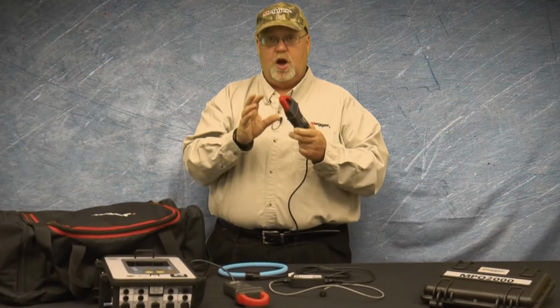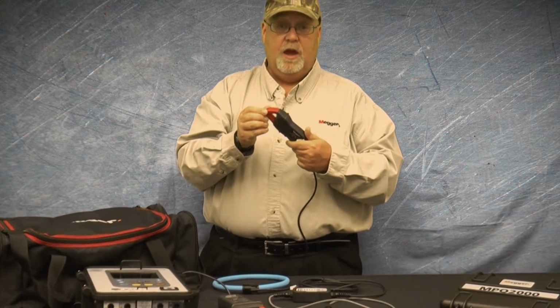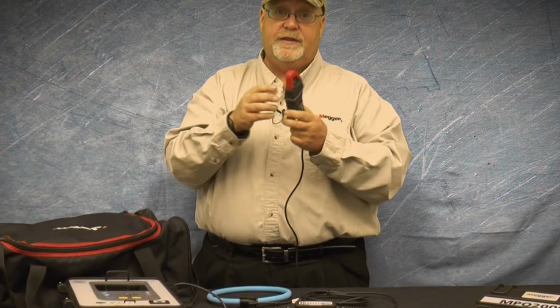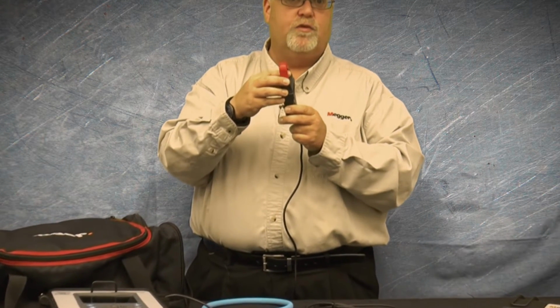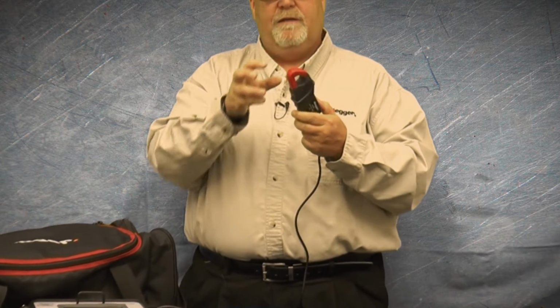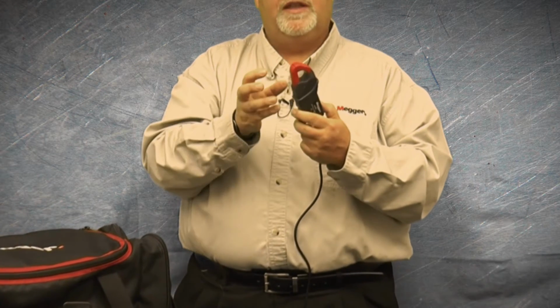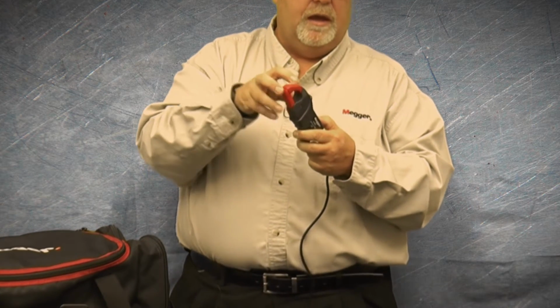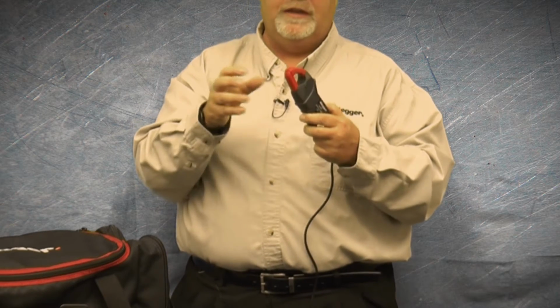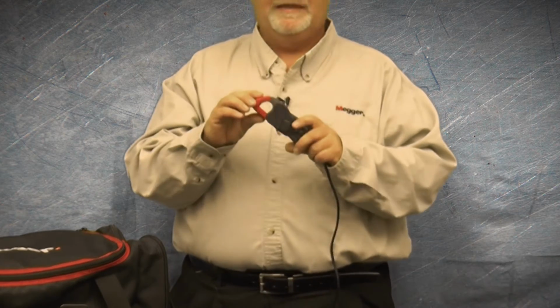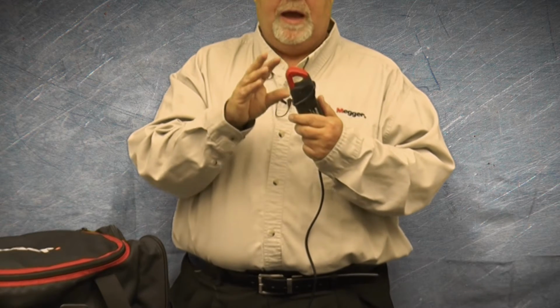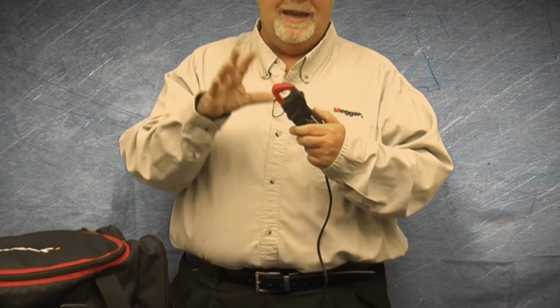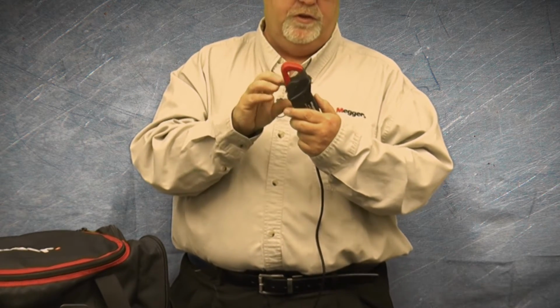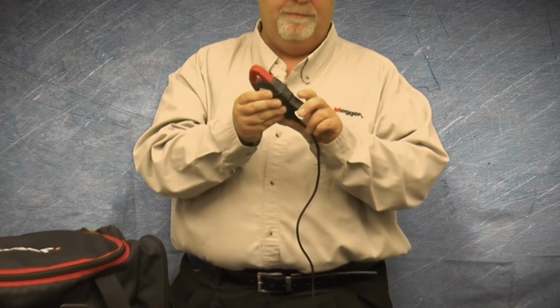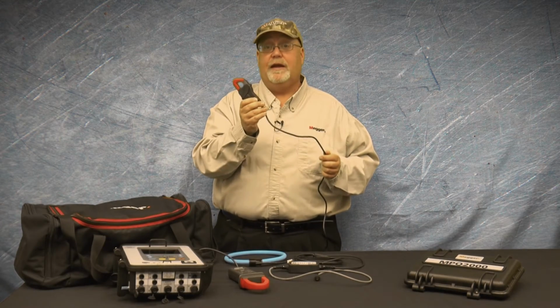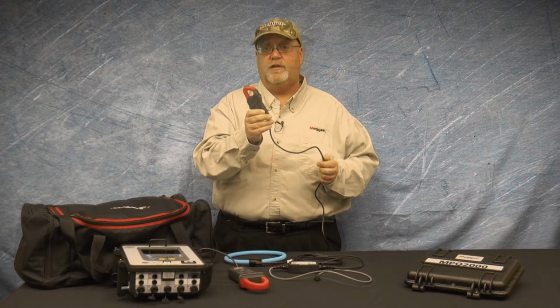The split core current clamp is like a transformer. The current in the primary, in this case, the wire that the CT is around, induces a magnetic field in the core, which is then transferred to the secondary, inducing a proportional current in the secondary. The split core CT is a passive CT with a high permeability core. It's the changing magnetic field that induces the changing current in it. This type of current clamp can be only used to measure AC current.